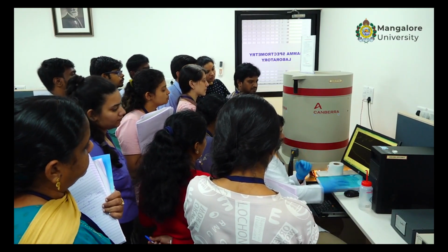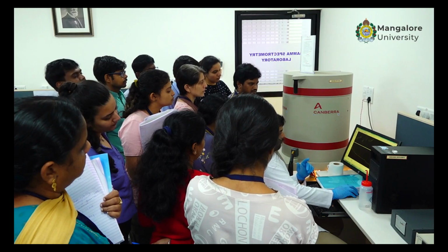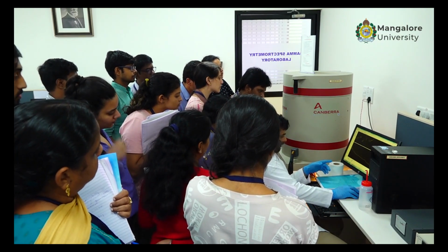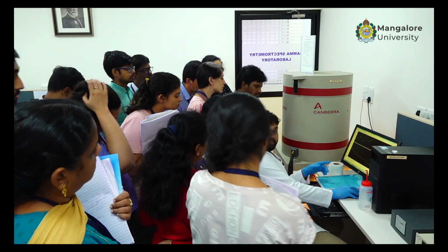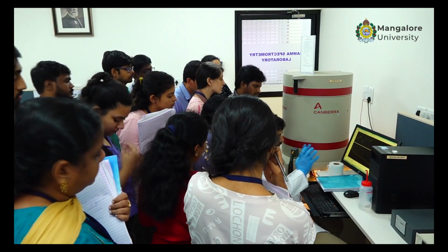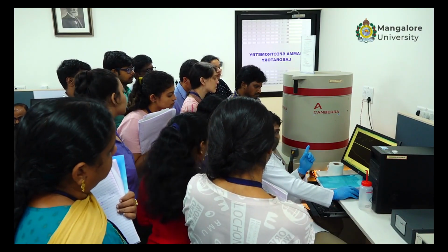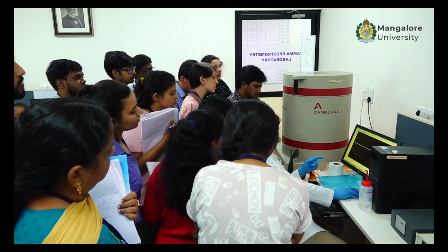So this is how we do one ROI. Now here you get two values. You can see there is integral area. There are 67,896 integral counts of this peak, but the Compton corrected count is 36,987.